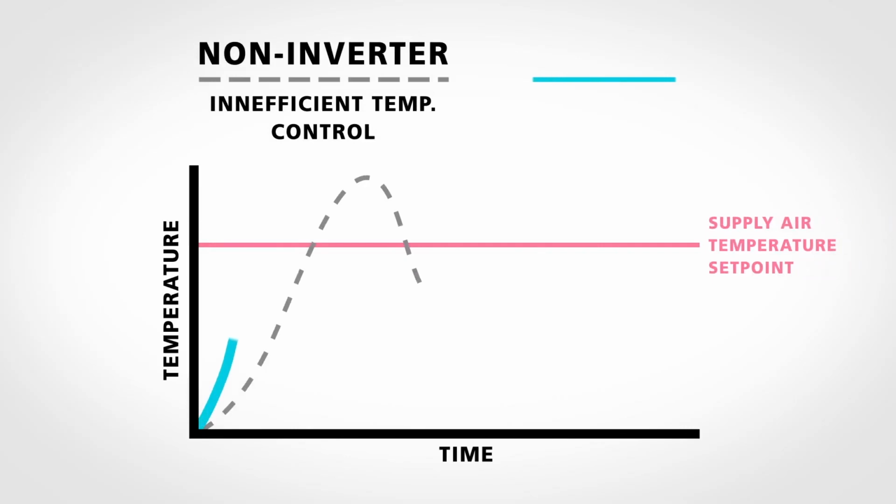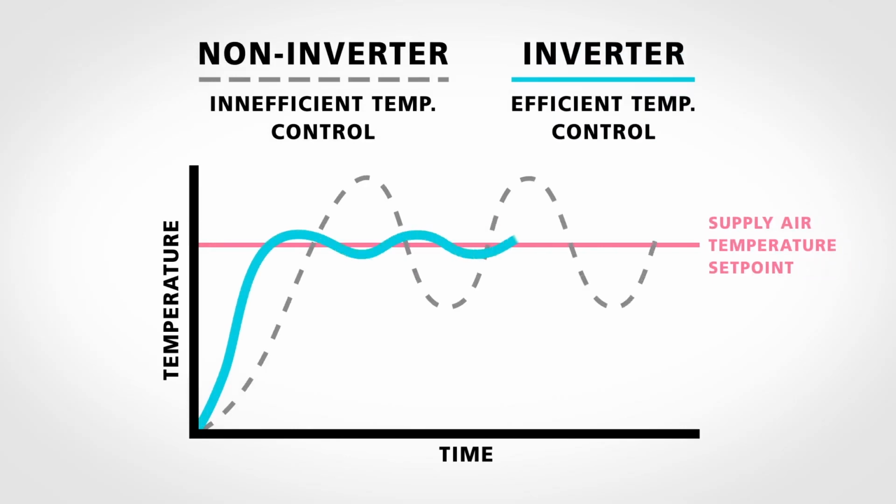Capacity control is achieved by changing the electrical frequency going to the compressor or fan motor, which reduces the speed and energy consumption. When a vapor refrigerant travels through a compressor, it increases in pressure and temperature, increasing the energy within the refrigerant. Now, the difference between the temperature leaving the compressor and the temperature entering the compressor is called lift. The higher the lift, the more energy is required. Inverters slow down the compressor, reducing the lift and energy use.